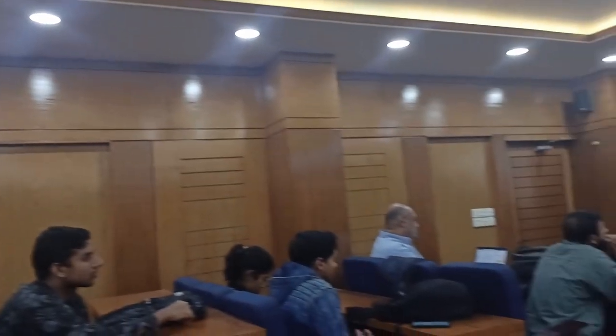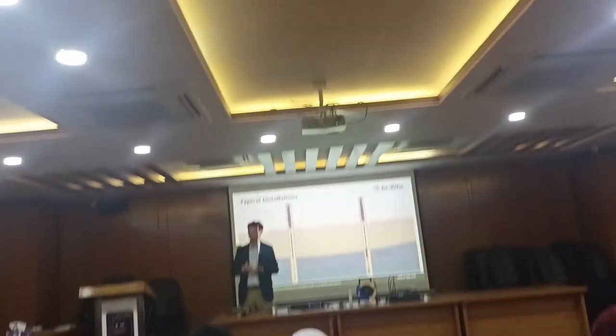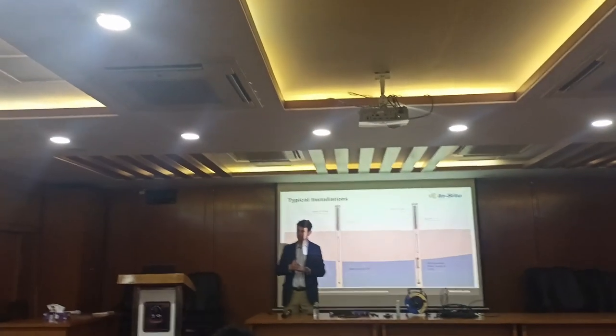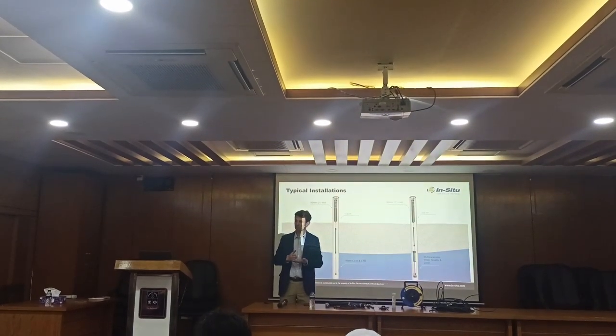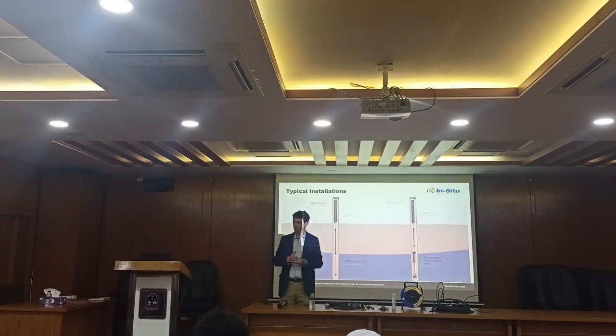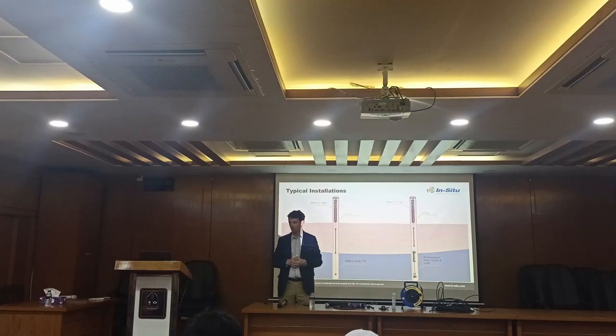So it depends on your sensor. That's the critical part here. What we typically recommend is based on guidelines we have to provide. However, what we've seen in the field and in actual operations is that you need to calibrate when you start seeing changes in your data that may not be explained by natural phenomena. Typically, pH has the shortest calibration time period. Your standard operating procedure may say you need to calibrate every day, every week, or before every deployment—whatever it may be. That's what you should go with.